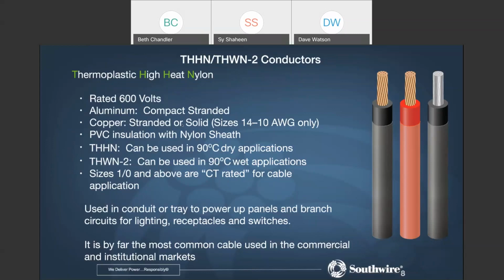Now on copper, it's available with stranded or solid stranding, if you will, for the small sizes, the branch circuit sizes, 14 to 10. Above that, you'll be looking at stranded only. So this is a PVC insulation with a nylon sheath. The N in the product name stands for nylon. If you go back in time a few decades, the product was originally made just with thicker PVC and without the nylon. So that's the T. Typically, those were just THW conductors. We still make those today for products like submersible pump cable. But for the general purpose conductors, at least here in the U.S., I believe all the major manufacturers have switched over to this nylon jacketed type of construction.